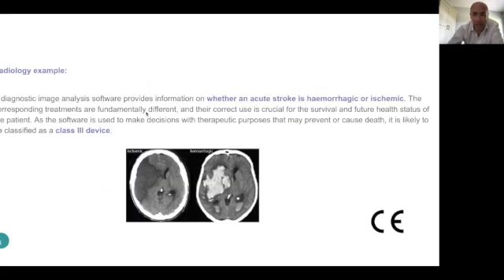By the way, I just want to add, the regulations specify that the highest possible risk, however unlikely, is the one that classifies your device. So if there's any chance that your device could cause a death, you will be in a higher risk class, unfortunately.